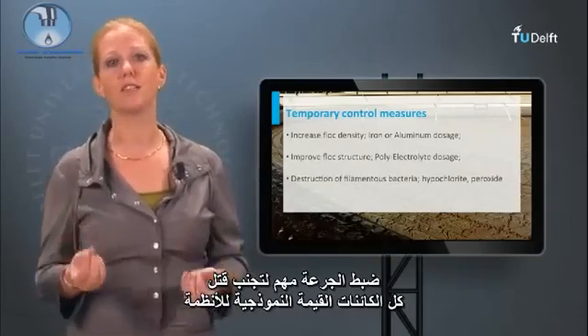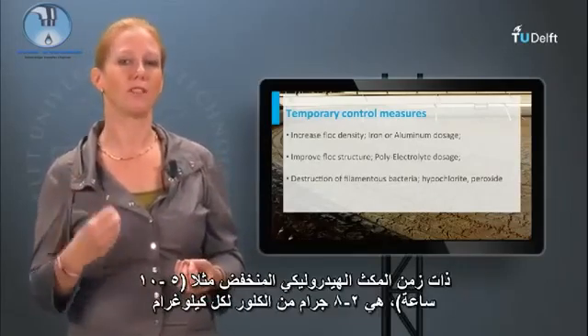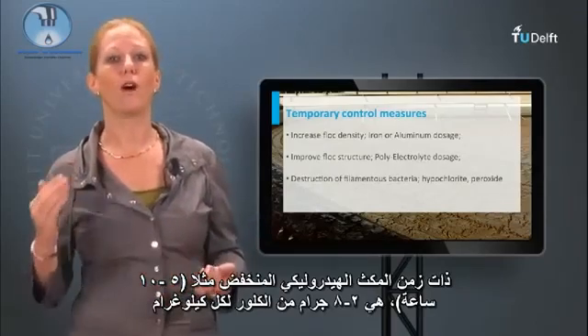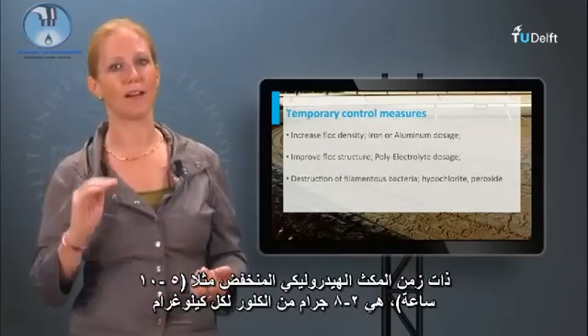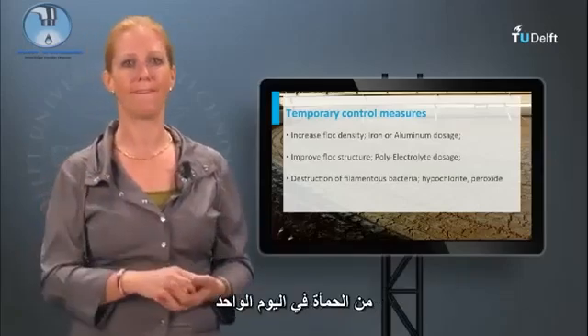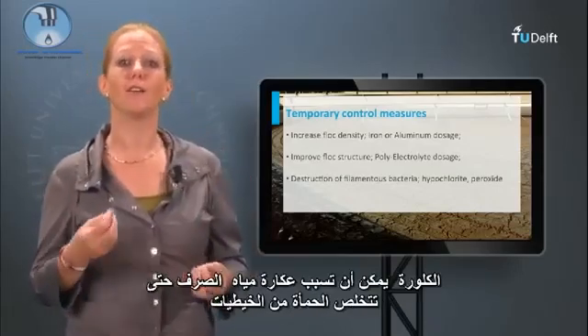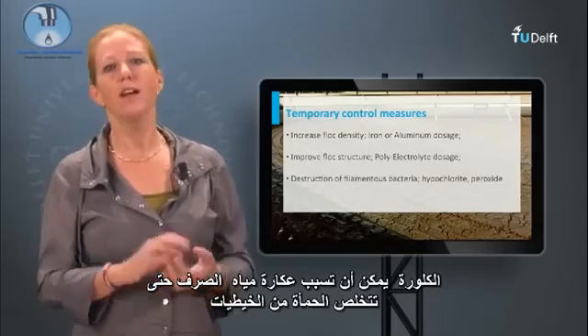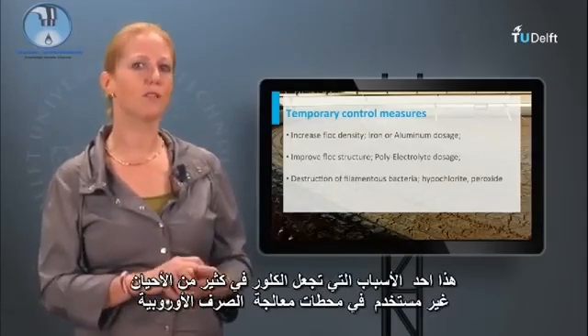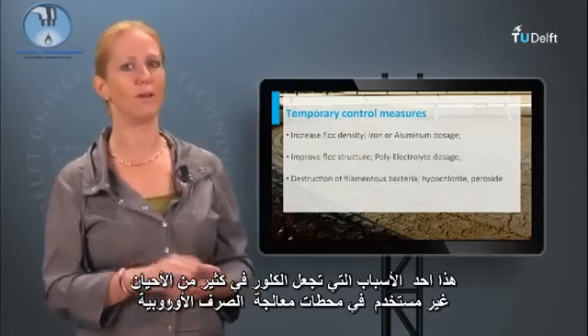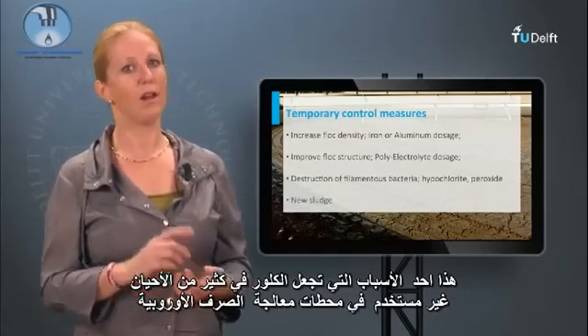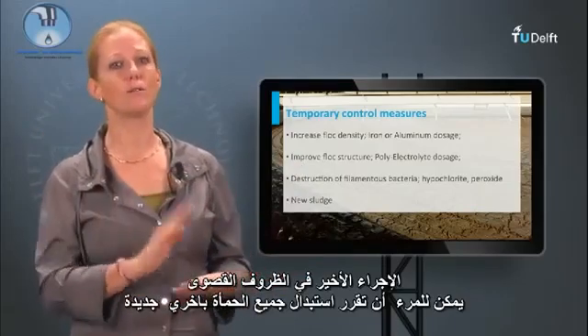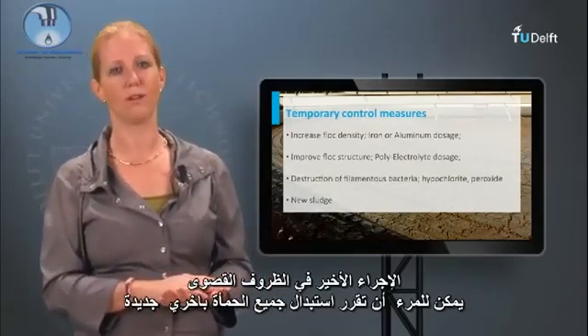A typical value for systems with a low hydraulic retention time, like 5 to 10 hours, is 2 to 8 grams of chlorine per kilogram sludge per day. Chlorination can cause turbid effluent until the sludge is free of filaments. This is one of the reasons why it is not often used anymore in European treatment plants. As a last measure in really extreme circumstances, one could even decide to replace older sludge with new one.